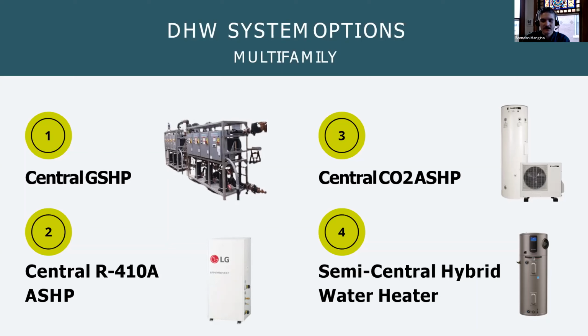The last system we looked at was a semi-central hybrid water heater system. So this design would have included ducting, a chain of these together, venting the supply and exhaust air for the heat pump into the hallway, and adding a little bit of supplemental electric resistance. We decided that was just way too complicated. If we didn't get the space heating completely balanced, we could have some cold spots. And we figured that since we were ducting inside the building, cooling that space down, the impact on our overall COP was just going to be too great, and we decided against it.